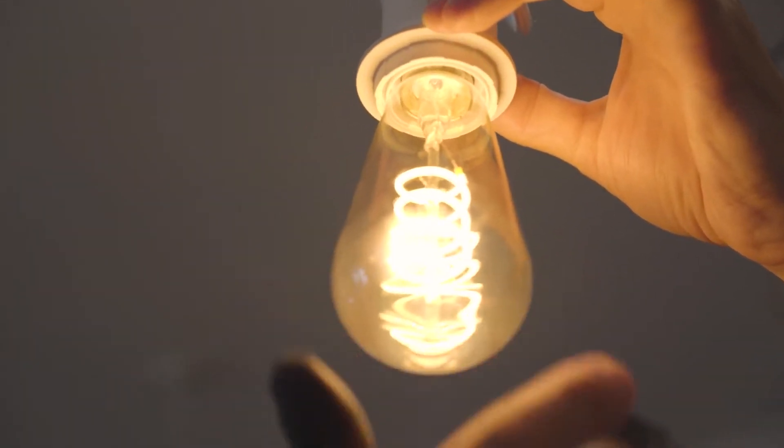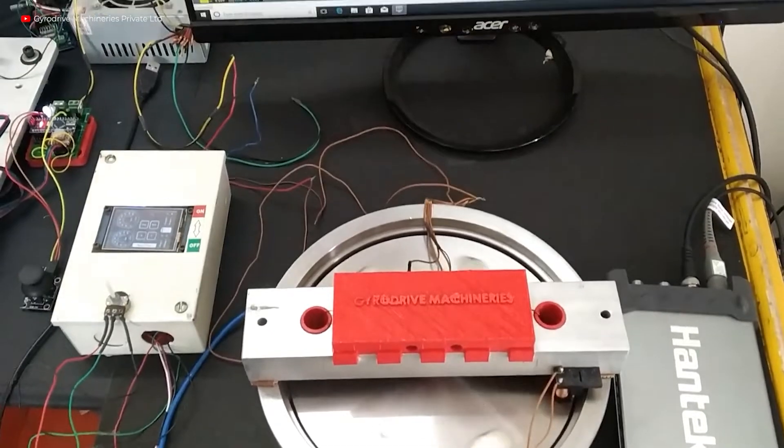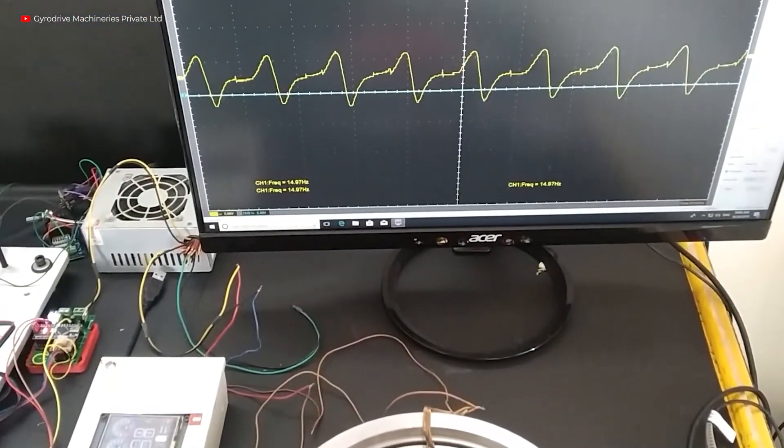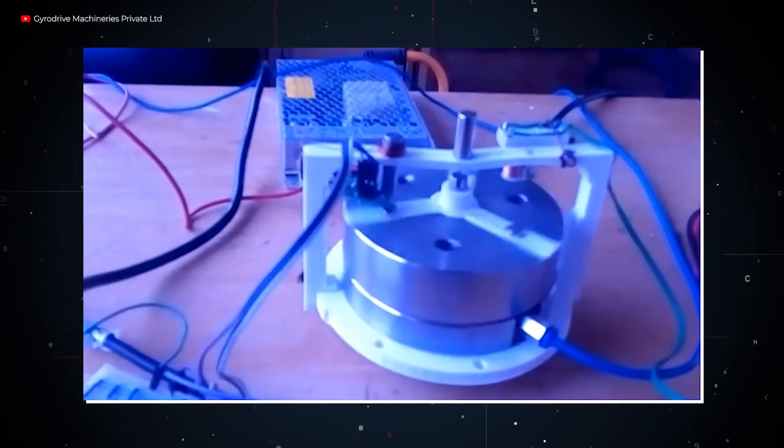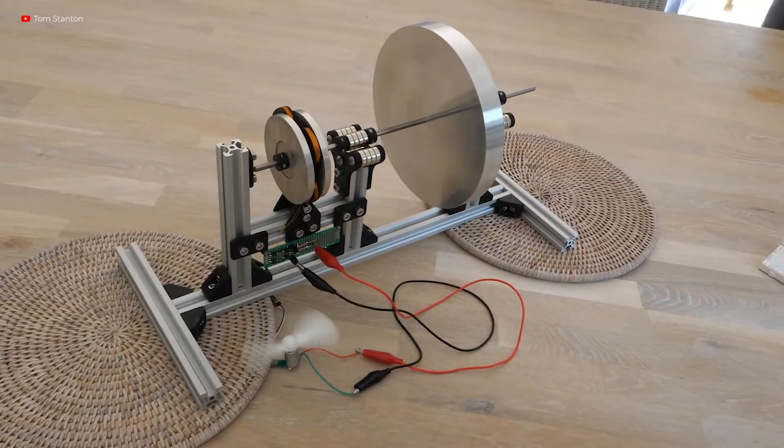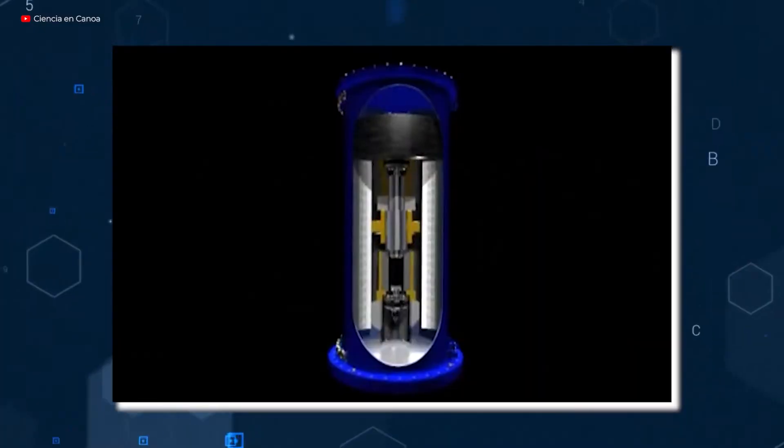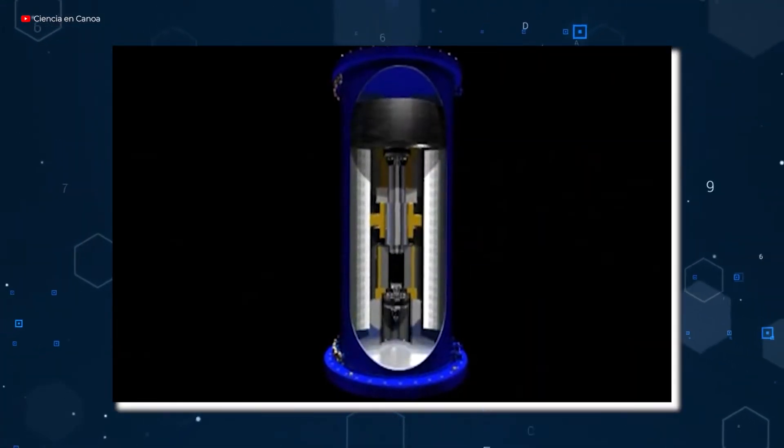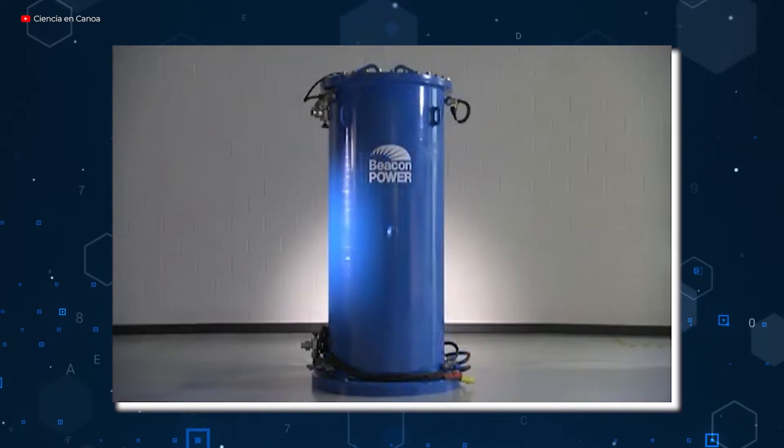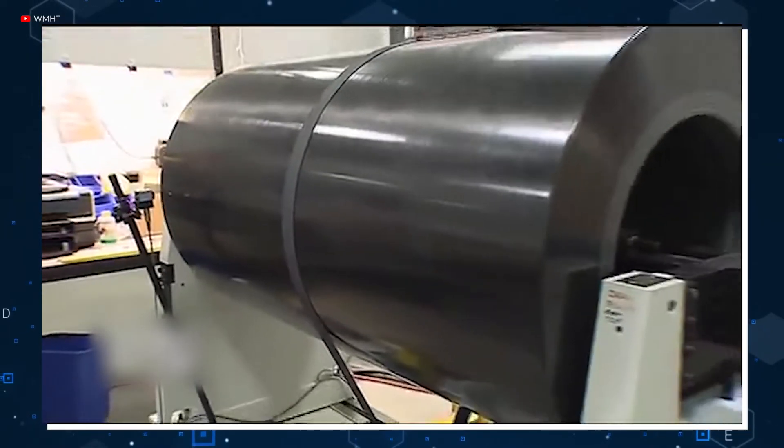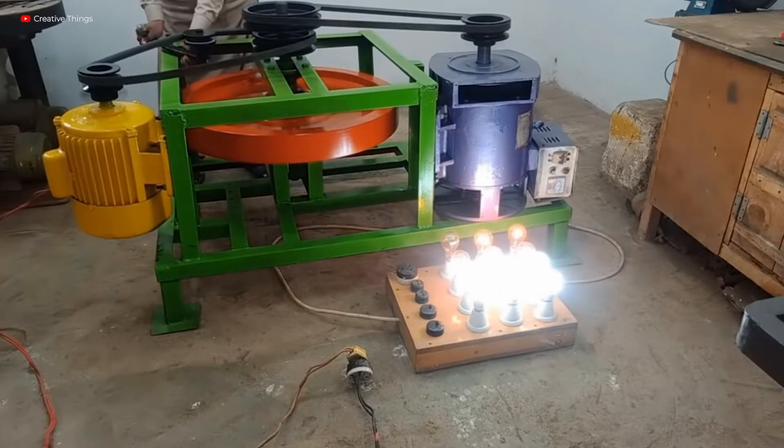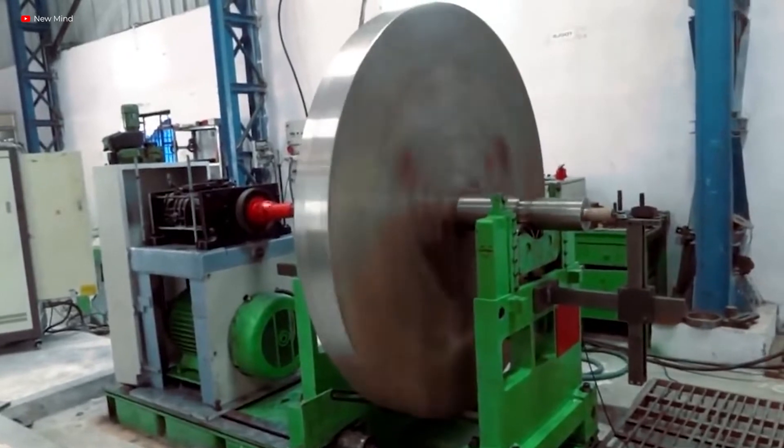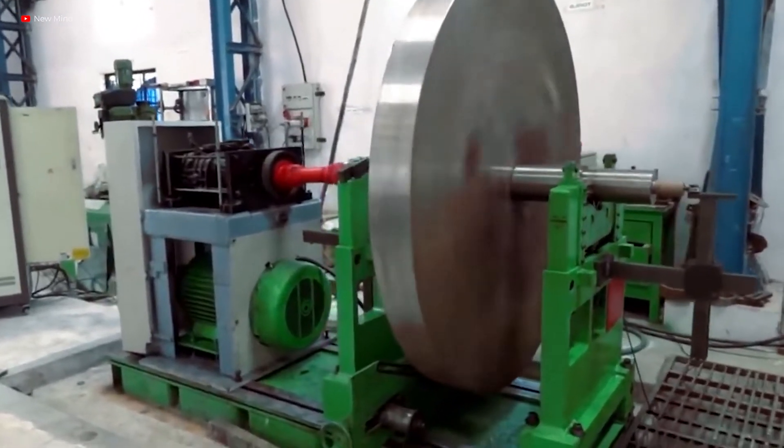High-power flywheel operation is based on advancements in power electronics, notably in high-power insulated gate bipolar transistors (IGBTs) and field-effect transistors (FETs). While the wheel's speed, mass, and shape influence the stored energy, the power electronics in general establish the restrictions on input and output power. Because fewer individual components are required with these high-powered devices, the power electronics package can be equivalent in size to the flywheel plus motor generator combo.